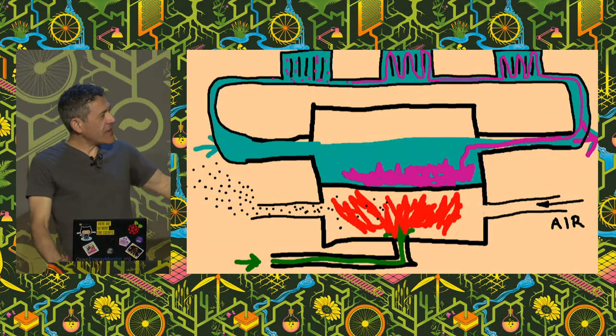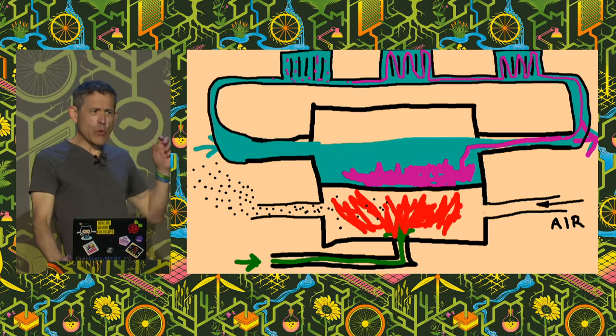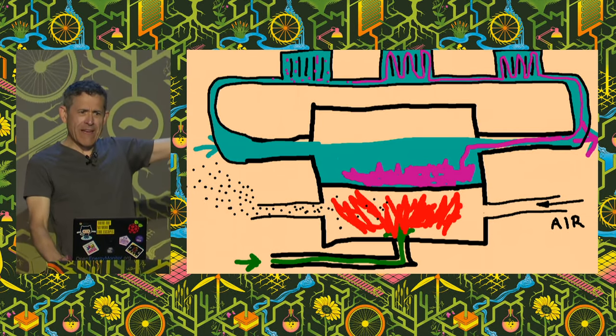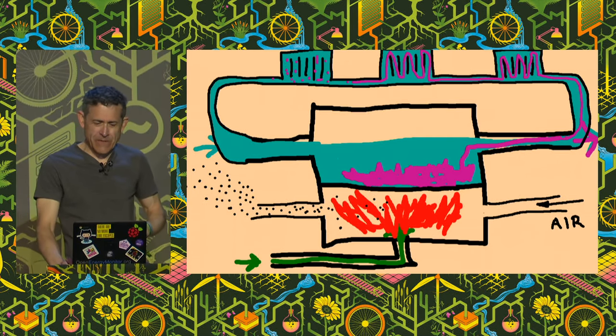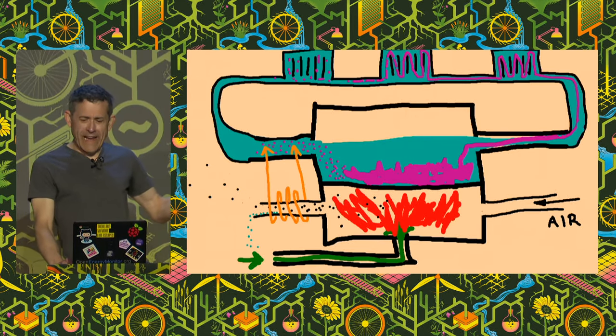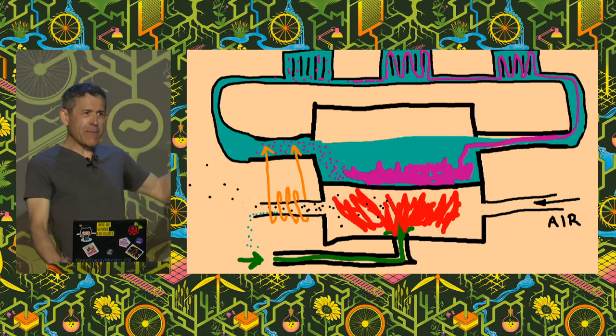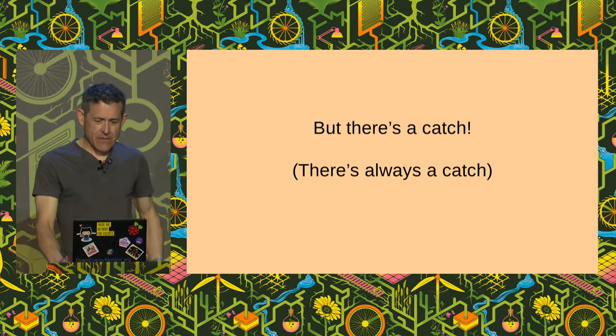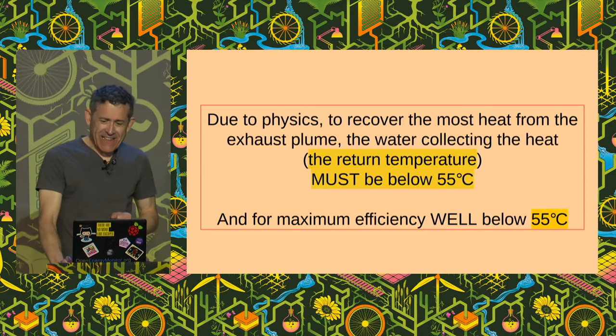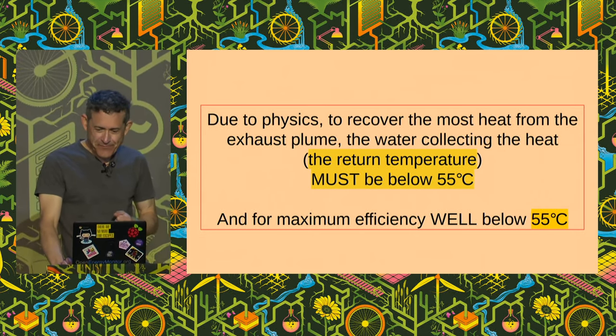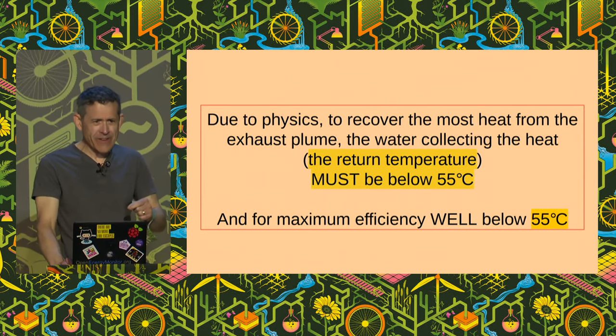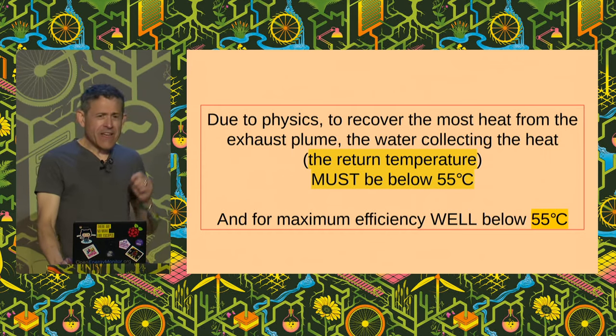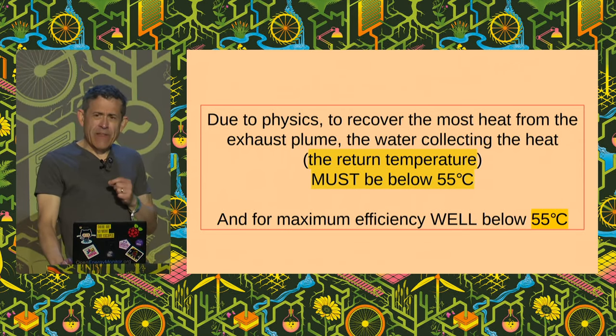Condensing boilers were invented to recover the heat that's in those two water molecules that are escaping normally straight outside your house, which then condense into a trickle of cool water as they give up the heat they contain. The condensing part captures the heat out of that vapour as it's escaping and puts it back into the return water, which heats it slightly, so it saves gas. But there's a catch: due to the latent heat of condensation, in order to get that water vapour to condense back into water, the return water's got to be below 55 degrees Celsius, otherwise nothing happens.